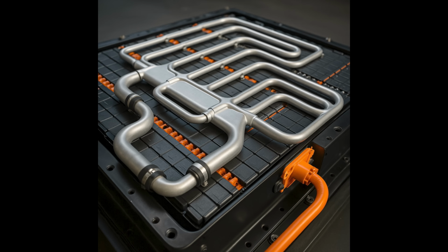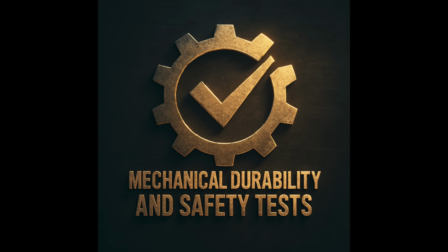Failure modes include pump cavitation and vapor lock, radiator airflow restriction, reservoir pressure regulator failures, non-uniform thermal spread leading to localized hotspots. Let's now dive into mechanical durability and safety tests.